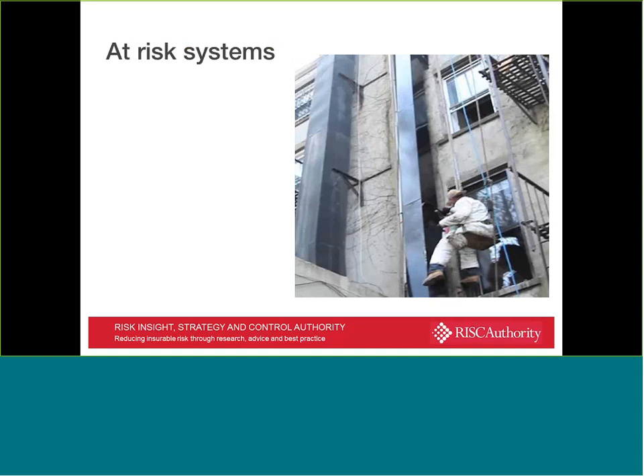When systems are identified where cleaning can't be done effectively due to the lack of access panels, sadly we're no longer allowed to drop small children into the extract ductwork to clean, although some people do have to clamber in there from time to time. The idea is that we cut access panels and allow them to clean from there. But in circumstances like that, it's clearly important that the panels are cut where they need to be and that cleaning can be done effectively.